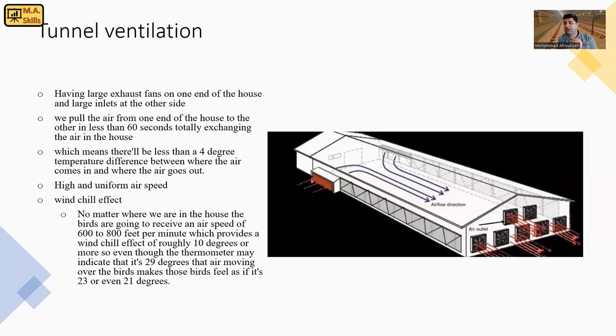In addition, by doing tunnel ventilation, we're creating wind chill effect. It means that maybe you're measuring temperature and the thermometer indicates, let's say, 29 degrees. But because we're creating air speed and air movements at 600 to 800 feet per minute rate, the birds will feel cooler - they'll feel 23 or even 21 degrees. Your thermometer shows 29 degrees, but your birds are feeling 21 degrees. It's the wind chill effect created through tunnel ventilation.